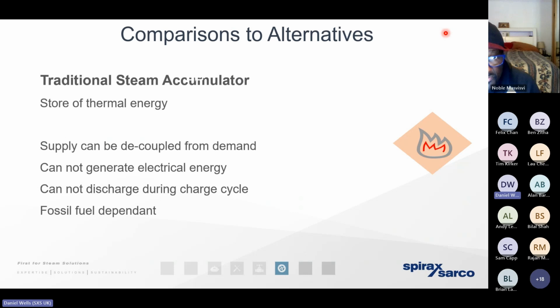Accumulators are very, very commonly used in breweries and the chemical sector, for example, when we need a huge release of thermal energy very, very quickly. We pressurize that hot water using any surplus steam. And then when we need that steam for the process very, very quickly, we can achieve it by depressurizing that hot water. Fantastic store of energy. The problem is we would generally be using steam that is produced from a gas boiler in order to charge that accumulator. So as great as it is, it's not helping us with our decarbonising journey.